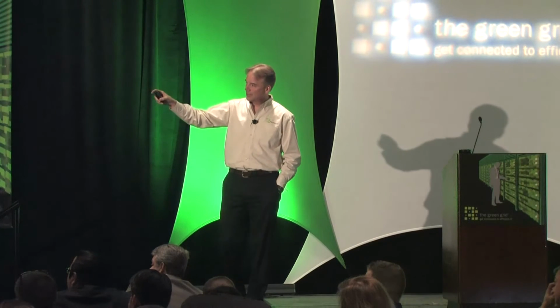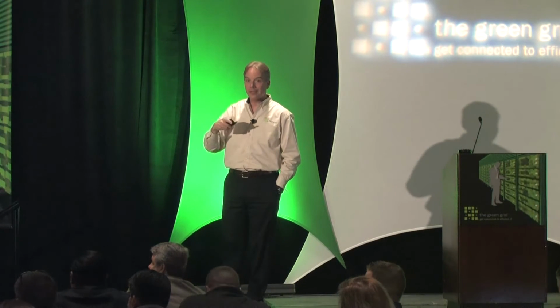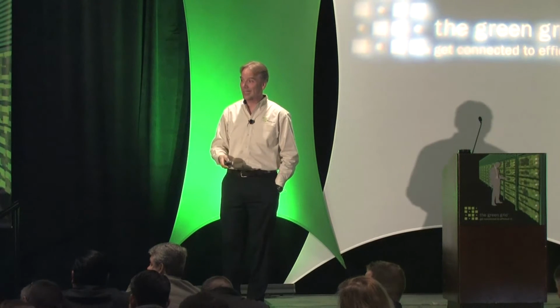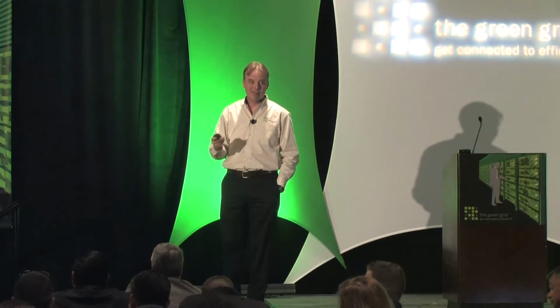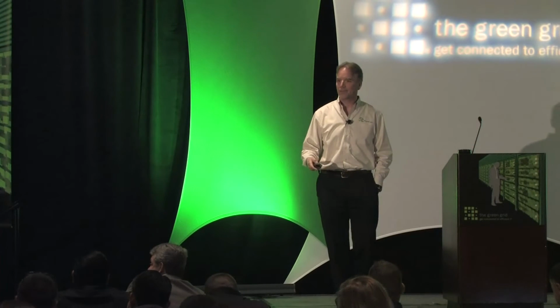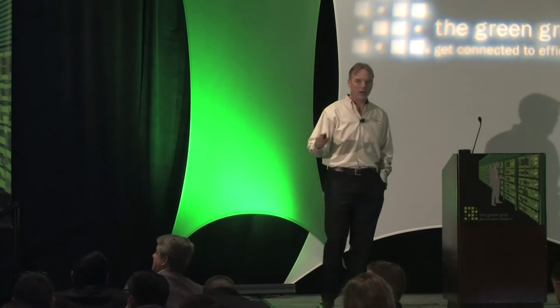You see those numbers? This right here is the low, 1.04. Remember, it's 119 Fahrenheit outside? Okay? We have 1,920 servers in there. It's 26 kilowatts of cabinets sustained at that point, and it's using outside air to cool. All right? Then, at the mid, and that's the maximum that we're getting out of that container in the worst possible conditions, because it had slightly rained that morning. Okay? 1.044 for an extremely dense environment on the roof exposed to the sun.